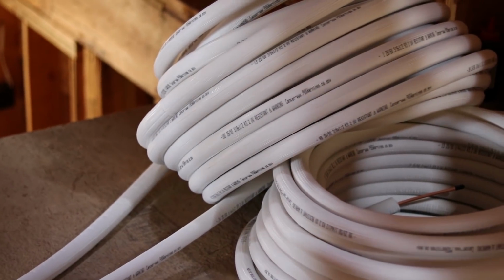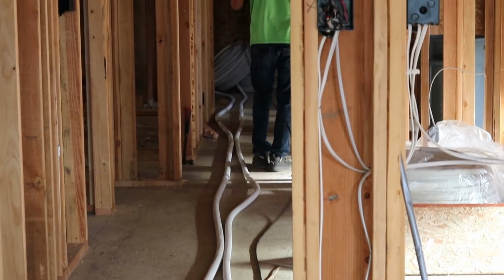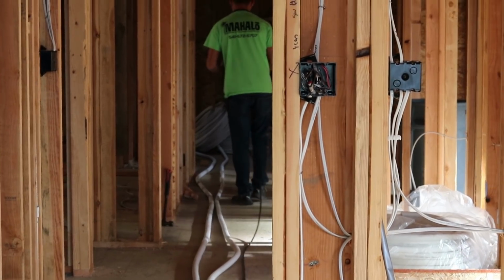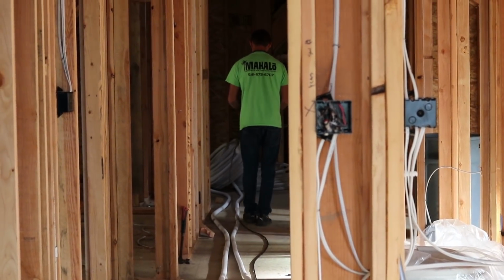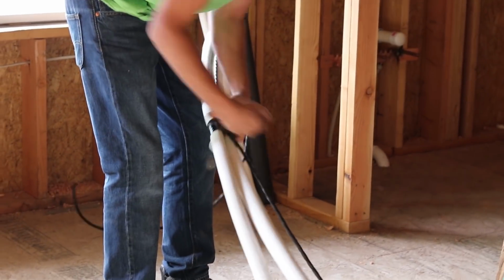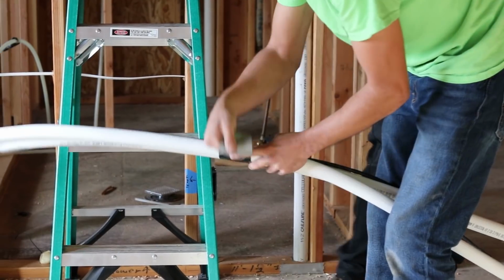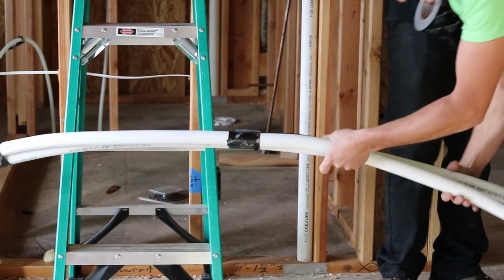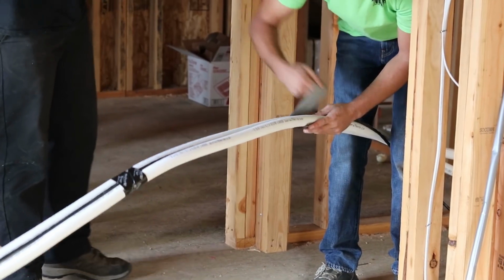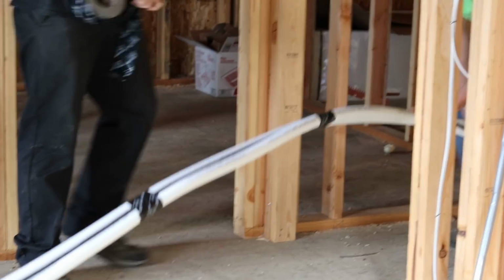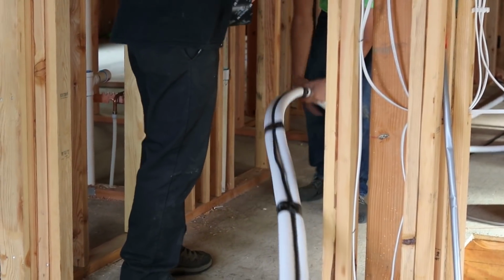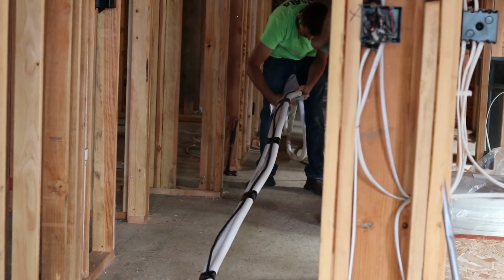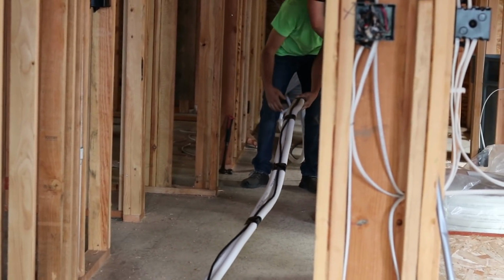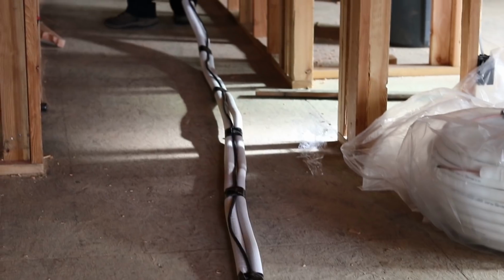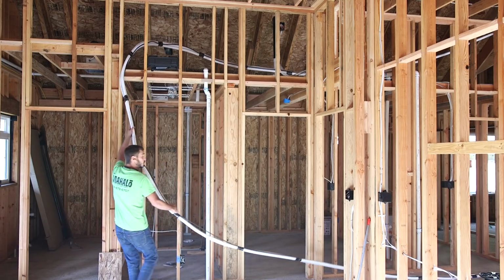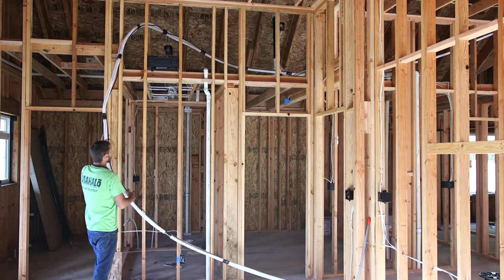The first part of this system to be installed are the refrigerant lines that connect each head unit to the outdoor unit. These are two malleable copper pipes, well insulated, that carry the gas to and from the outdoor unit, which houses the compressor and condenser. Along with these refrigerant lines there's a control wire so the two units can communicate. This control wire also powers the indoor unit, so you don't have to have your electrician run another power line to each of the heads.